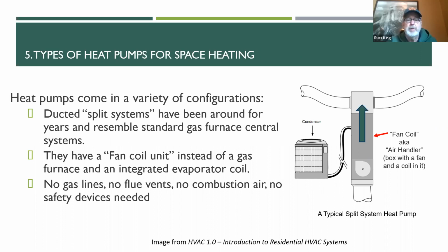Ducted split system heat pumps have been around for a long time, okay? When you look at them, they look like a regular gas furnace, but you'll see there's no gas line going to it. There's no flue vents and things like that. They've been around for a long time. I lived in a house that had one for a long time back in the 80s. And instead of a furnace, they have something called a fan coil unit, which has a big fan in it, which is what pushes the air through the ducts. And the coil, the evaporator coil, is incorporated into that box. Okay.